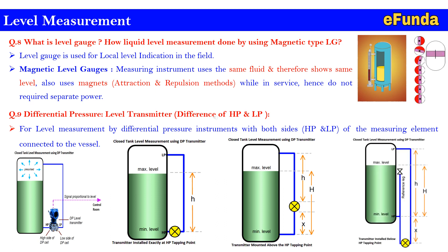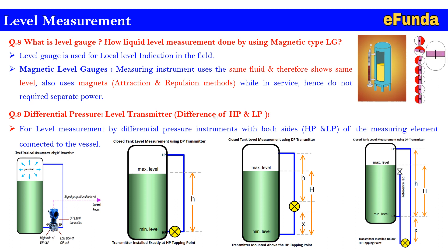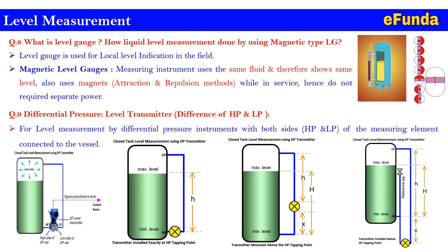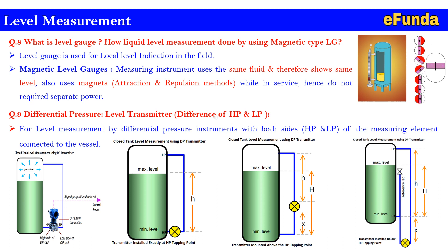The third configuration shows the transmitter mounted above the HP tapping point — this is non-preferable due to the chance of bubble formation in the impulse line. The fourth configuration has the transmitter installed below the HP tapping point, which always introduces an error that can be compensated by suppressing or elevating the transmitter zero.